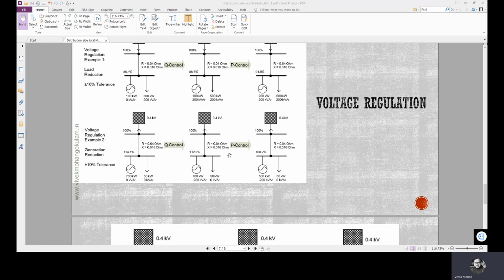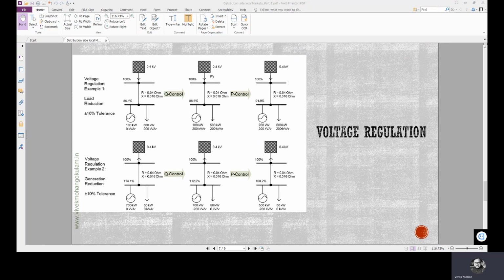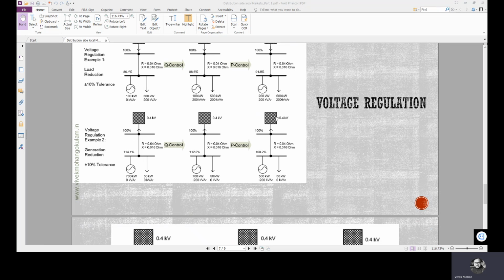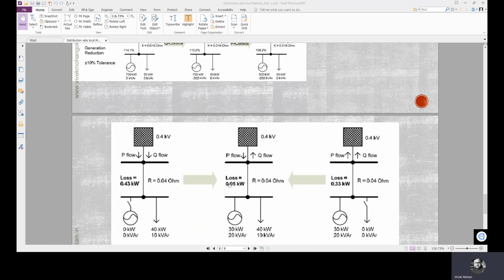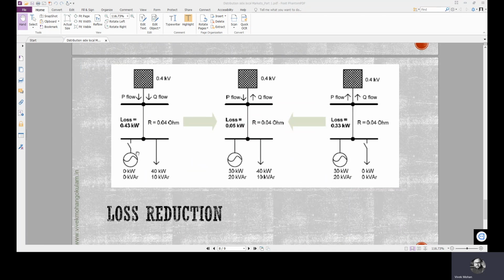The load is untouched. Now again, we are trying for active power control, similar to the case which we have seen above. The only difference was the direction of power flow. Here the direction of power flow is towards the upstream grid. Now from 700 kilowatts, the local power generation at the local node is reduced to 500 kilowatts. So again, you have a reduction in voltage, and it has now become 108.2%, which is within the 10% tolerance band. That's what is the voltage regulation service. Now coming to loss reduction, you can see three different figures here.